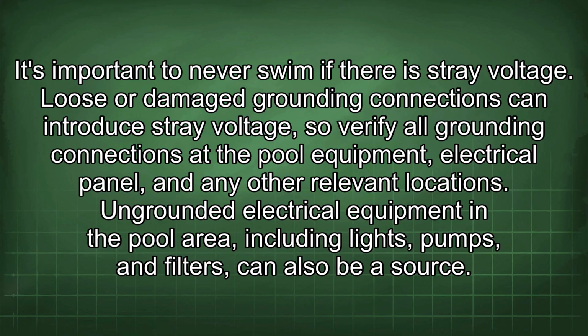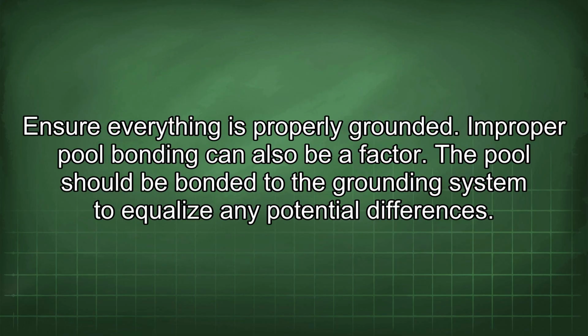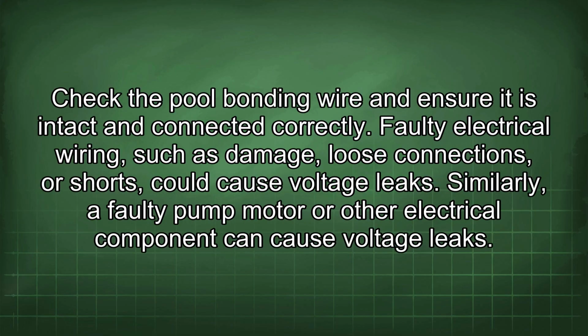Loose or damaged grounding connections can introduce stray voltage, so verify all grounding connections at the pool equipment, electrical panel, and any other relevant locations. Ungrounded electrical equipment in the pool area, including lights, pumps, and filters, can also be a source. Ensure everything is properly grounded. Improper pool bonding can also be a factor. The pool should be bonded to the grounding system to equalize any potential differences. Check the pool bonding wire and ensure it is intact and connected correctly.